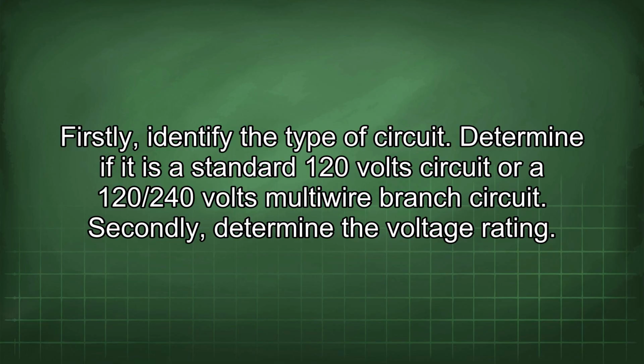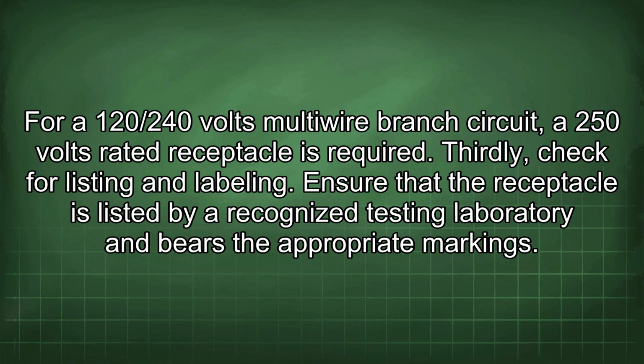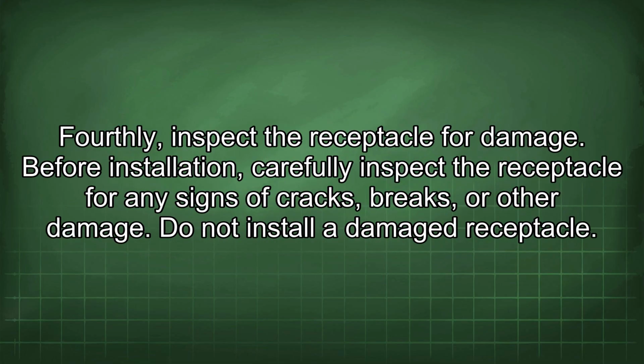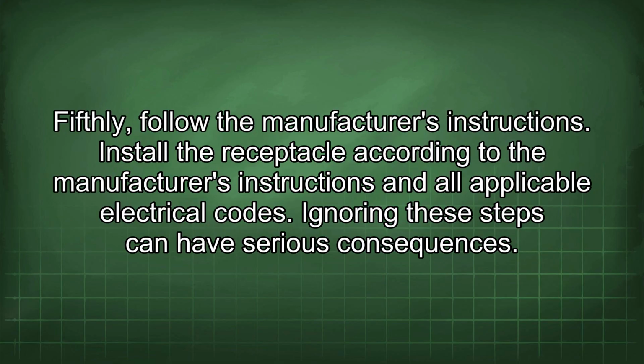Secondly, determine the voltage rating. For a 120/240 volts multi-wire branch circuit, a 250 volts rated receptacle is required. Thirdly, check for listing and labeling. Ensure that the receptacle is listed by a recognized testing laboratory and bears the appropriate markings. Fourthly, inspect the receptacle for damage. Before installation, carefully inspect the receptacle for any signs of cracks, breaks, or other damage. Do not install a damaged receptacle. Fifthly, follow the manufacturer's instructions. Install the receptacle according to the manufacturer's instructions and all applicable electrical codes.